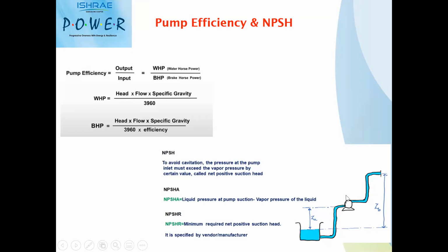So the pressure available here is called net positive suction head available at the site. This net positive suction head available is calculated based on your atmospheric pressure, which is acting on the fluid if it is an open loop system. So atmospheric pressure of 10 meters, which is water.